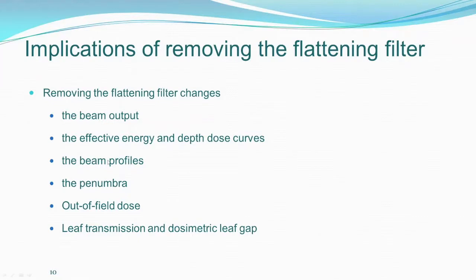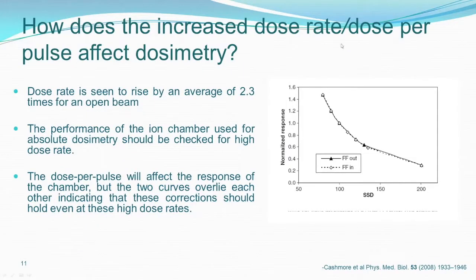Beam profiles undergo very different changes. The profile is not the same, and so how to measure the penumbra is a question. Out of field dose is advantageous to us. You also have to look at things like leaf transmission and the dosimetric leaf gap. So how does the increased dose rate or dose per pulse affect our dosimetry? Dose rate is seen to rise by about 2.3 times for an open beam in the case of FFF.